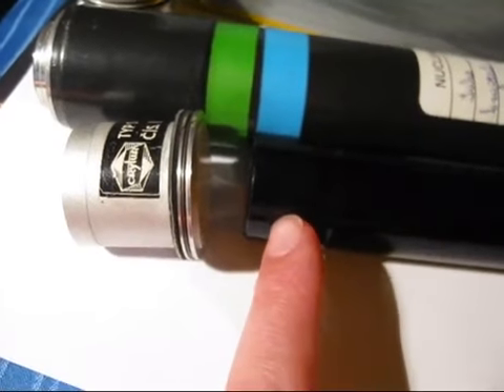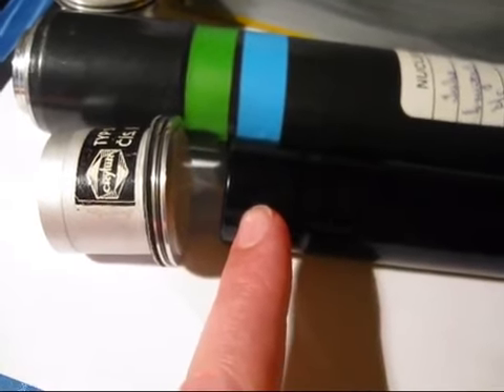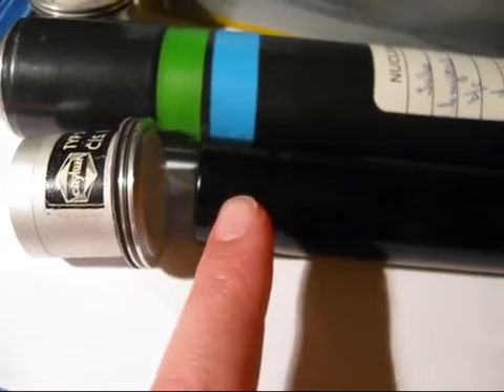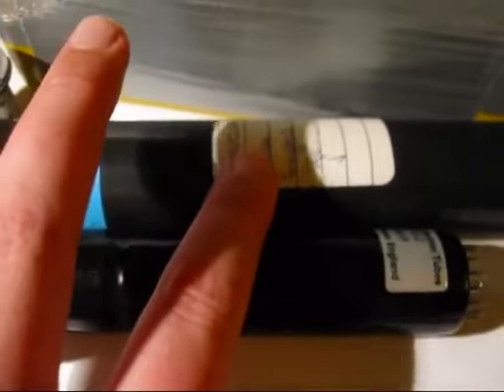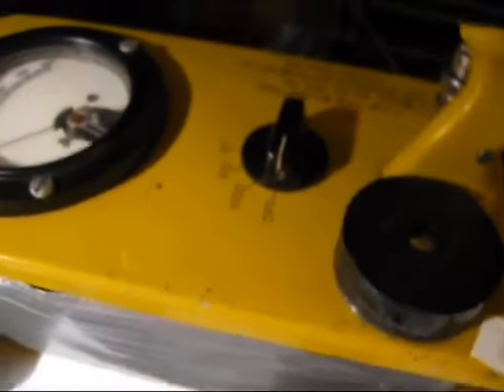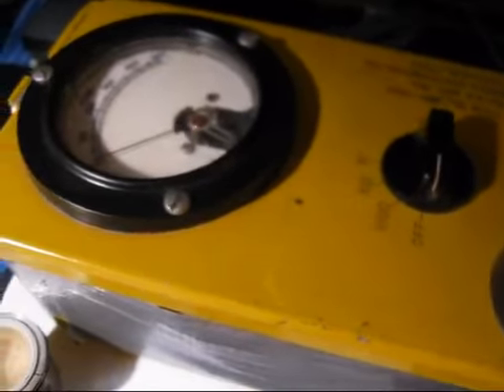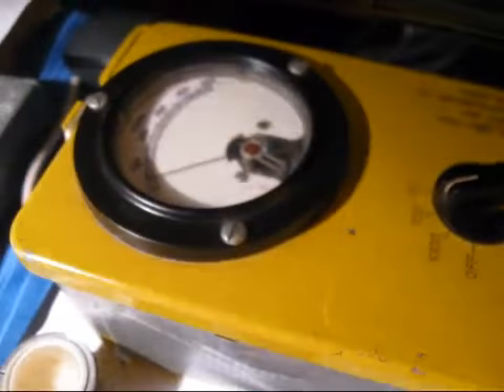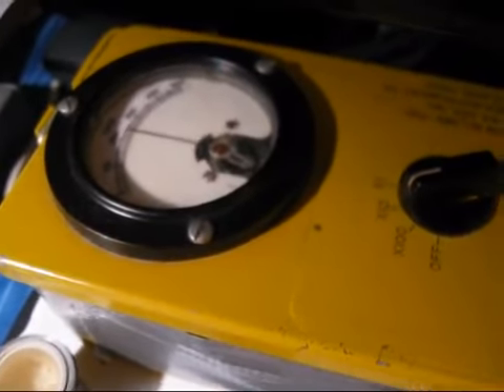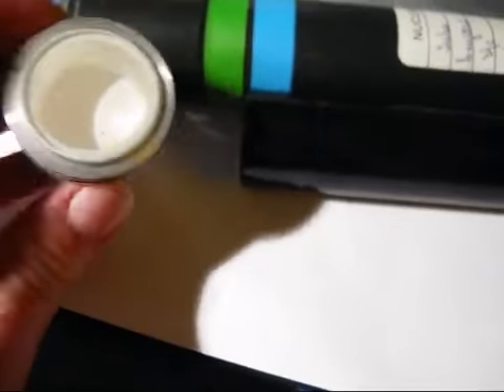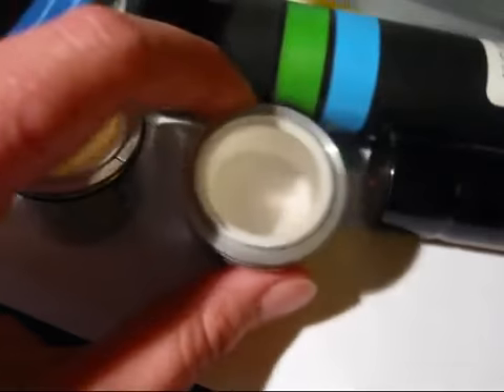Those little flashes of light will be registered by the photocathode that is in this stage, and the photocathode will thus release electrons, and the electrons will be accelerated by an applied high voltage such as 700 volts from this CDV700, and will be accelerated towards the anode and can then be registered by a device like this, amplified and then registered and shown as counts, impulses per second, for example, or impulses per minute. This device is highly sensitive. So that's how it works basically.